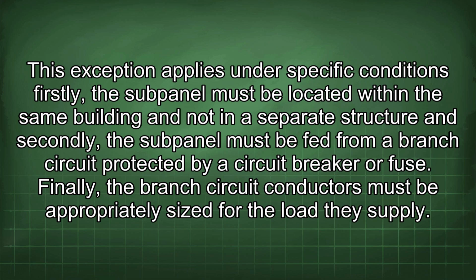Firstly, the subpanel must be located within the same building and not in a separate structure, and secondly, the subpanel must be fed from a branch circuit protected by a circuit breaker or fuse. Finally, the branch circuit conductors must be appropriately sized for the load they supply.